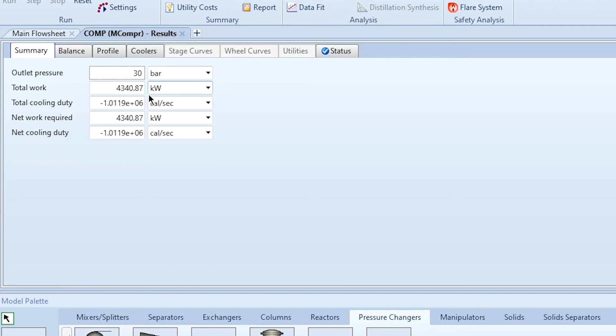You can analyze the system by varying efficiencies and varying the number of stages, and you can even optimize your multi-stage compression system to determine the optimal number of stages. Note that the number of stages is limited by the compression ratio, which typically exists between 2.5 and 3 — you cannot go below 2.5 or above 3 per stage.